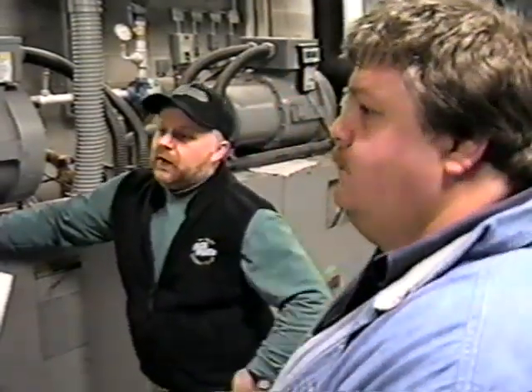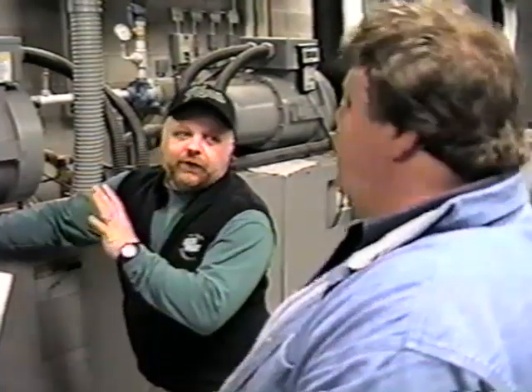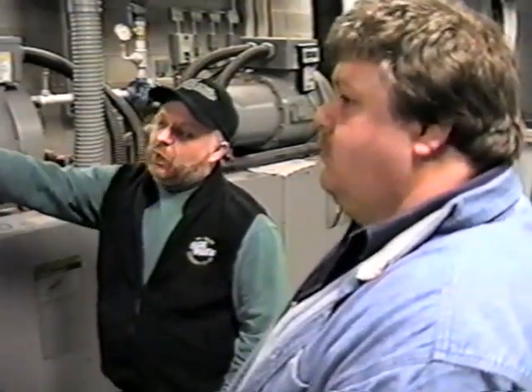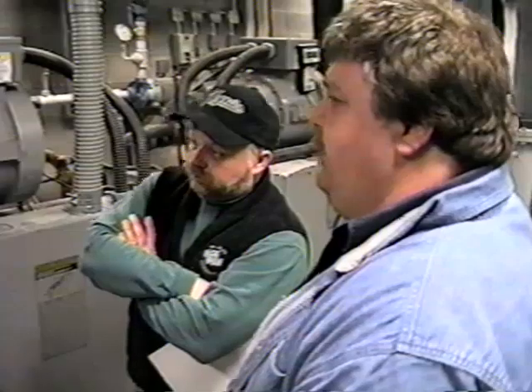What's that alarm sound like? Will we be able to hear it above everything that's running in here? Right now, that one I'm not sure. We just got a memo from the state saying that if that alarm goes off, we're not supposed to come in the room. Okay. But there's other alarms in here, so we were wondering if that should be wired to a light on the outside of the door. Actually, it should have a remote light or a horn. And I'm not really aware if they did that or not. We have to check with the electrician.